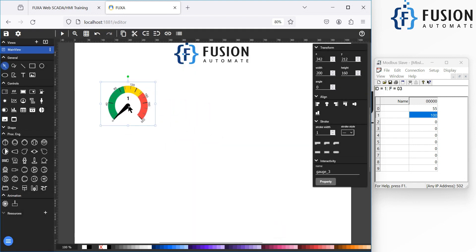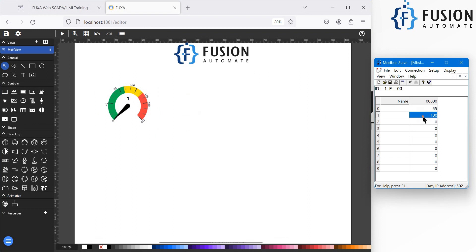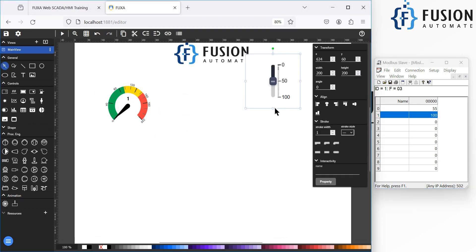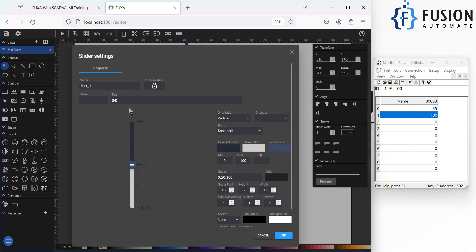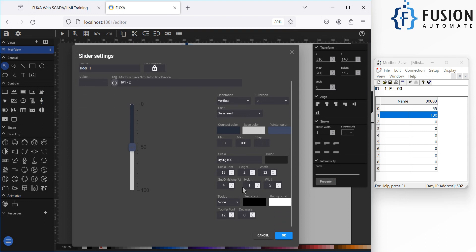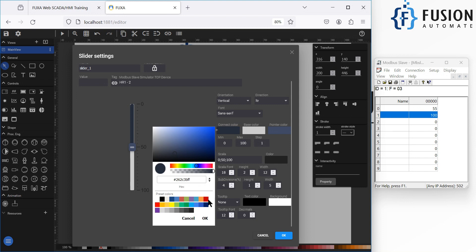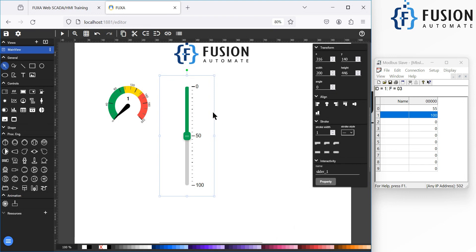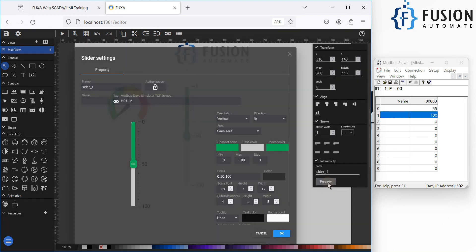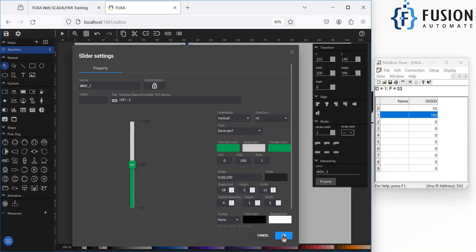To update values from FUXA SCADA for the second holding register at address offset 2, add a slider widget. In the slider properties, assign the tag 'Holding Register 1'. The scale is 0 to 100, the step is 1. You can change the color to green. If you want a reverse direction, you can set that in the properties as well.